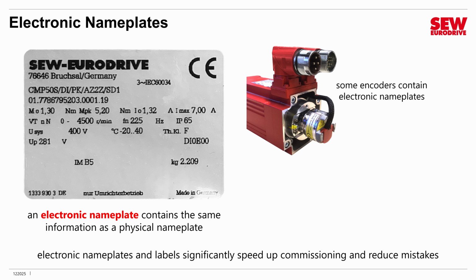Hiperface encoders are a common example of those that often do. What will happen is if you plug into the encoder, the VFD will be able to read the nameplate and use it during commissioning. Now there is one little gotcha with electronic nameplates and encoders. If a maintenance person swaps the encoder to a different motor, the nameplate goes with it. If that motor does not match the nameplate, then you've got a mismatch, and that means you could miscommission that motor. So you should always check the information that's coming back from the nameplate just to be sure it looks realistic before you accept it.